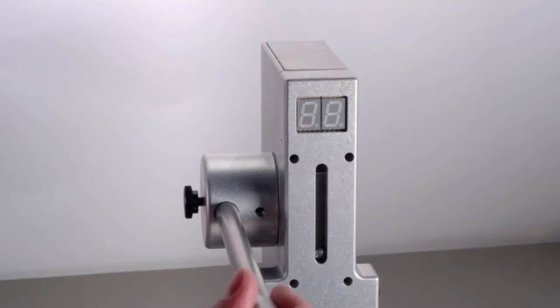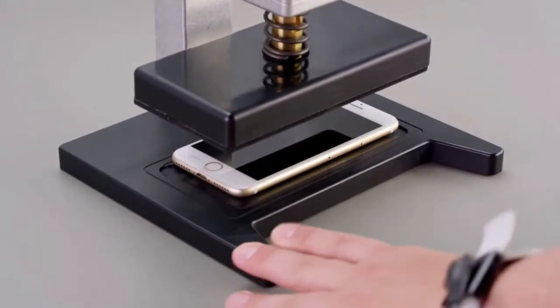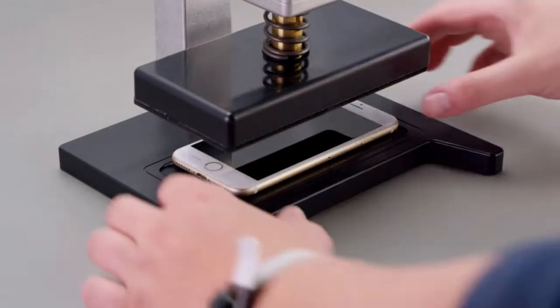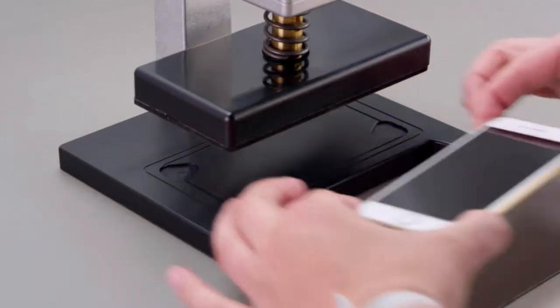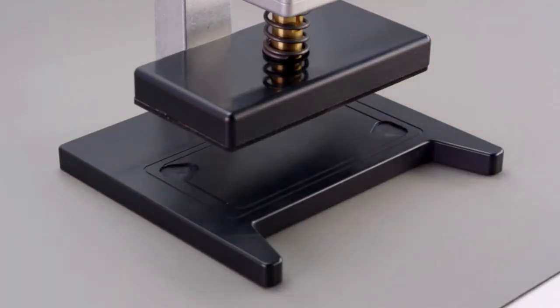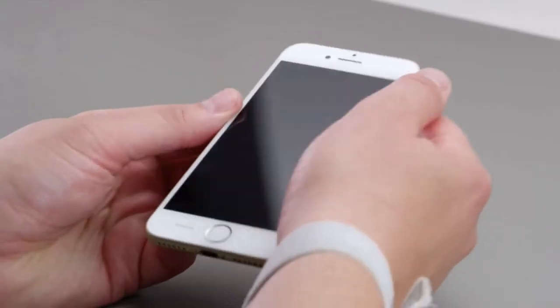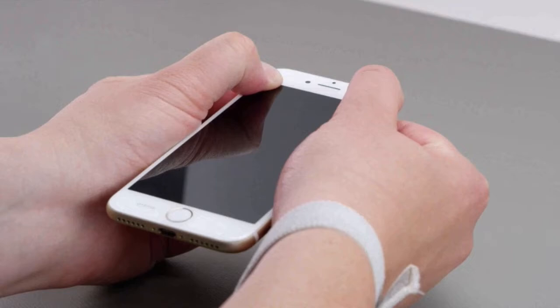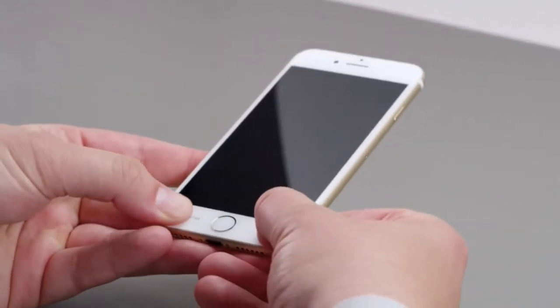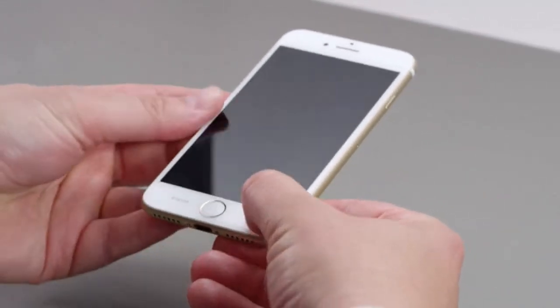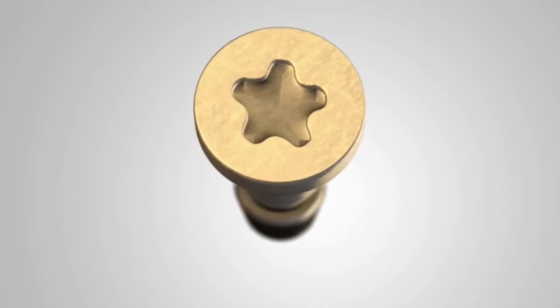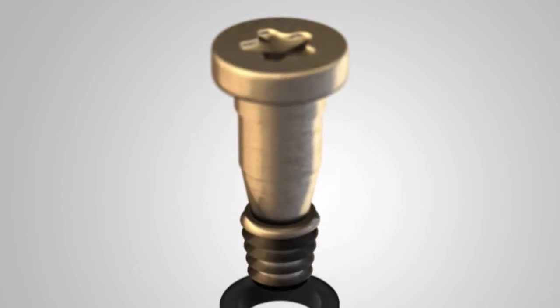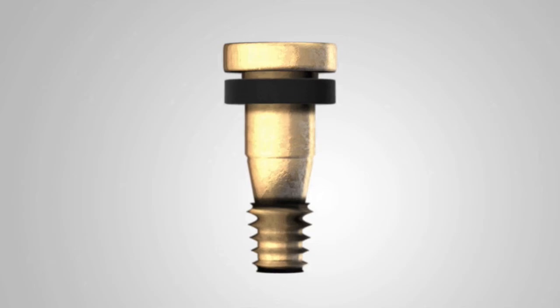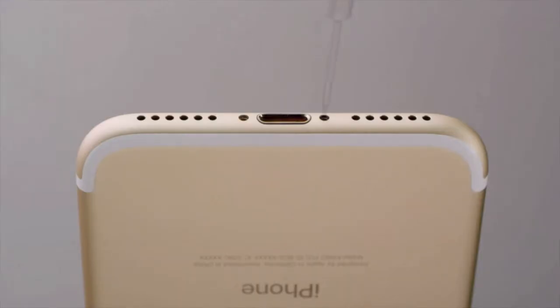Raise the lever. Display calibration may fail if this step is not completed. Remove the iPhone. Ensure that the adhesive has not leaked out between the enclosure and the display. Press firmly on the corners of the display. Verify that the gaskets are present on the new security screws before installation. Use the black torque driver to install 2 new security screws.